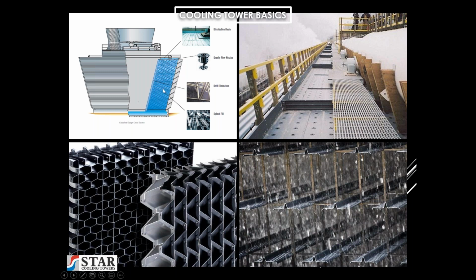Because of the intimate mixing of the air and water, there has to be a means of stripping out the water before it travels to the fan. So drift eliminators are installed to provide sudden changes in air direction for the water and the air droplets. The water droplets cannot make these turns. They impinge and film back into the wetted section of the cooling tower.